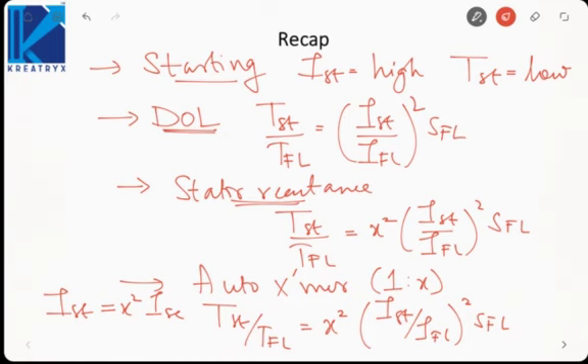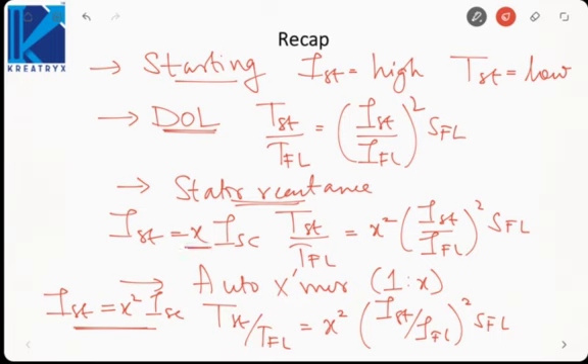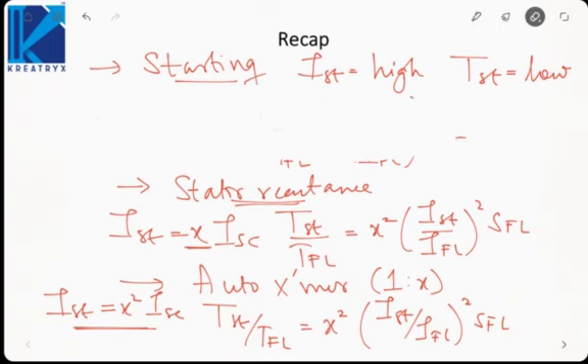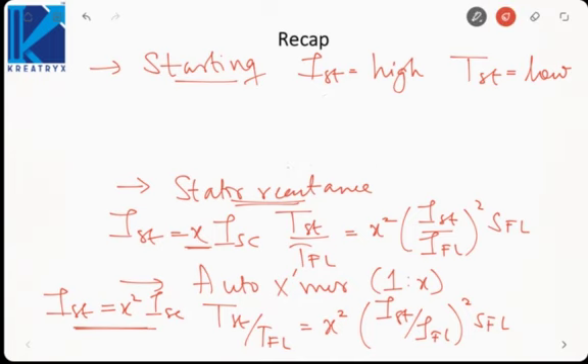There was a high reduction in current for the same reduction in torque compared to stator reactance. In stator reactance the starting current was x times I_short_circuit, so if x = 0.5 the starting current became half. But in the case of auto transformer, due to the x² ratio, the starting current became 0.25 times — a much greater reduction.